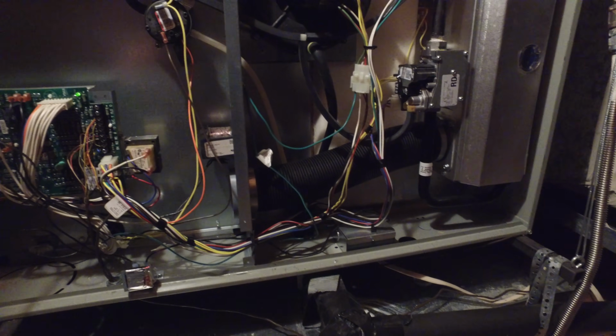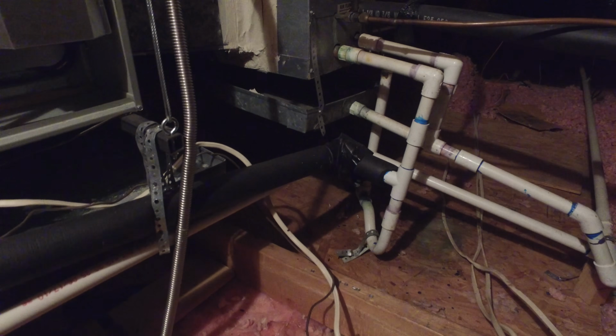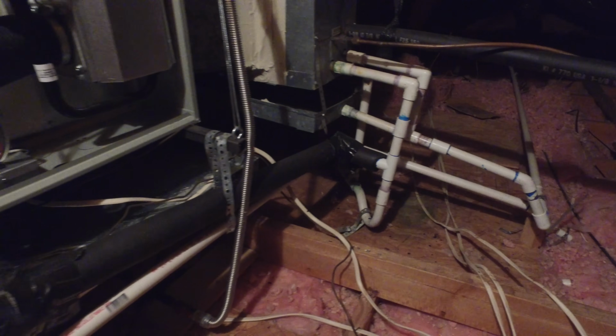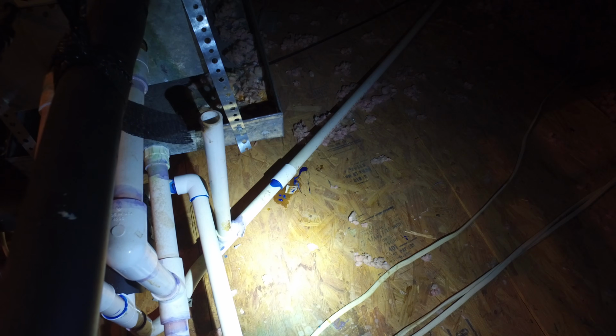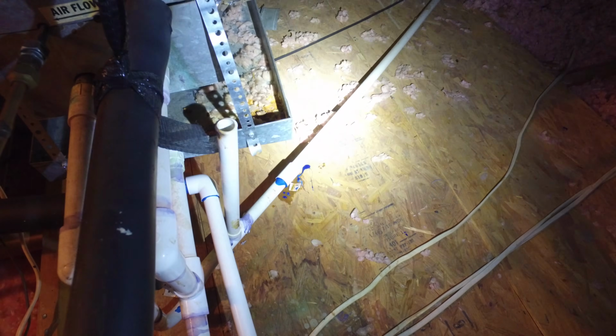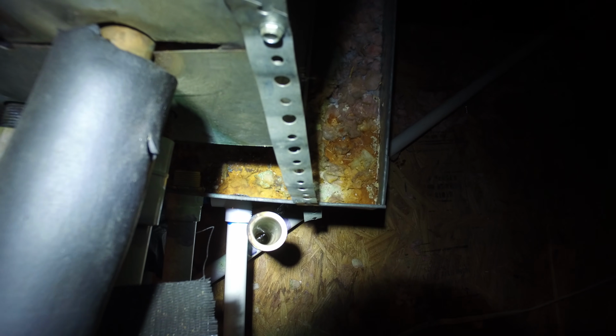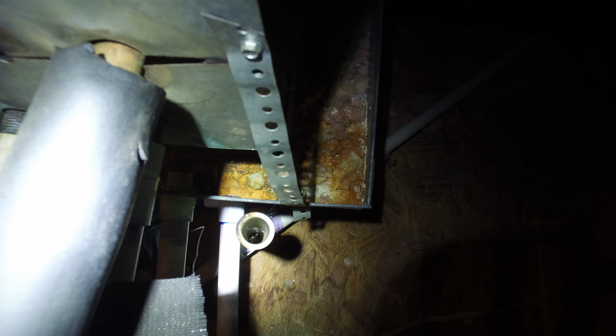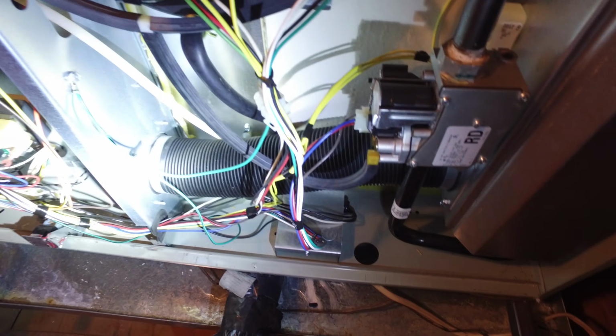So basically what ended up happening with this unit was I had a clogged drain line down here. This is the actual pipe right here. See, he made a repair on the pipe. He opened up the pipe and pressurized it with nitrogen to clear out some sort of clog in there. It may have been algae or something like that. But you can actually look down inside this pipe right here and see the water flowing, and that's good. You want to see good water flow. The water should be flowing down that drain, and that's condensation that builds up inside this heat exchanger unit.